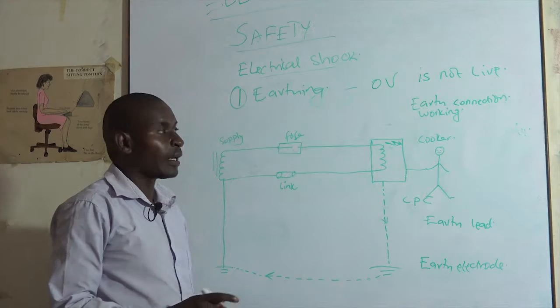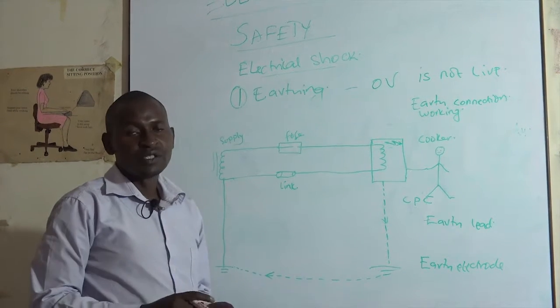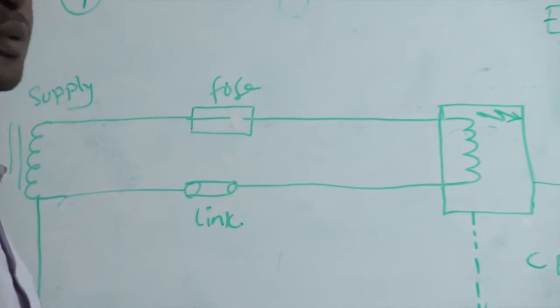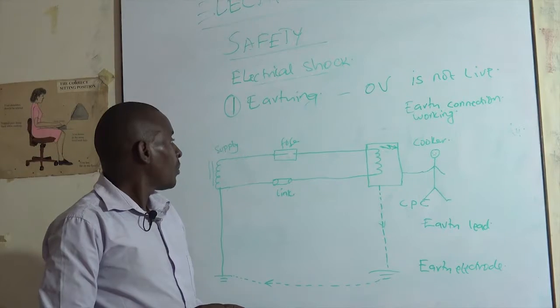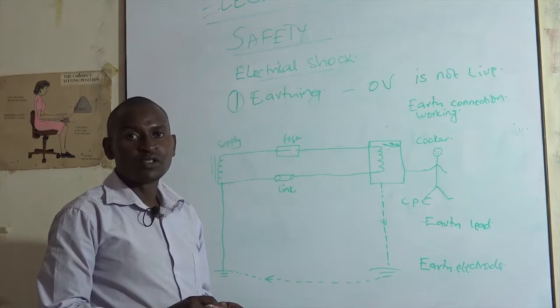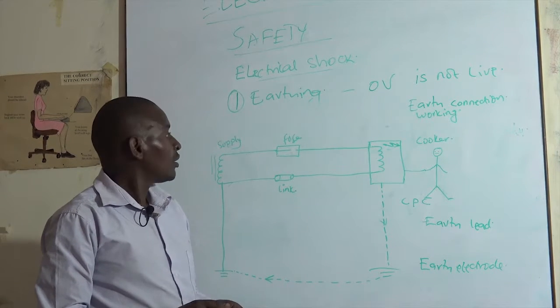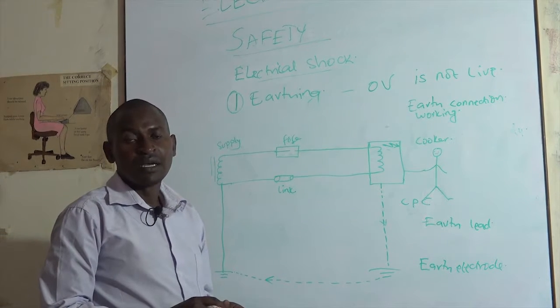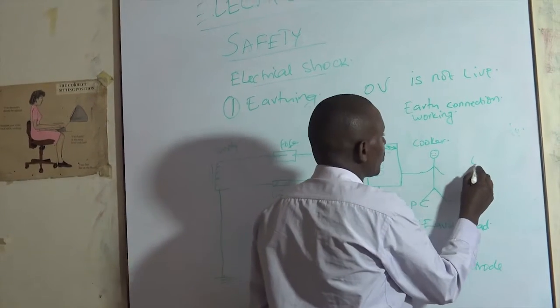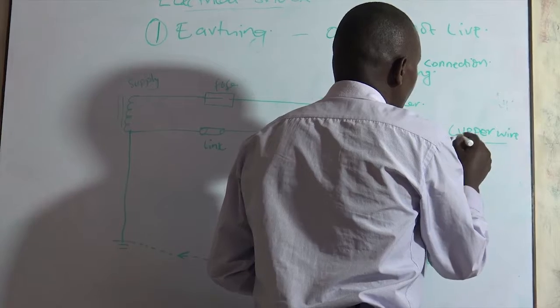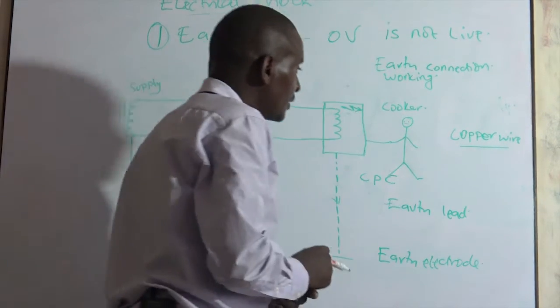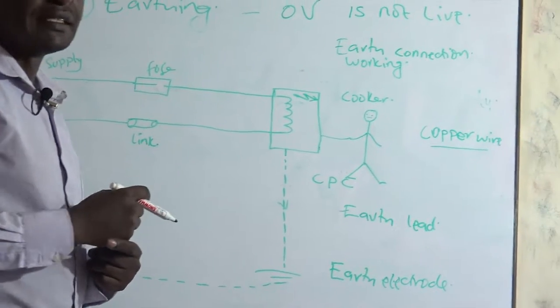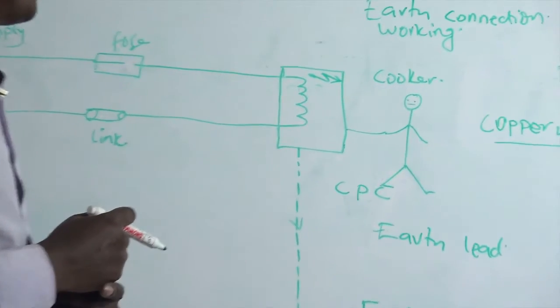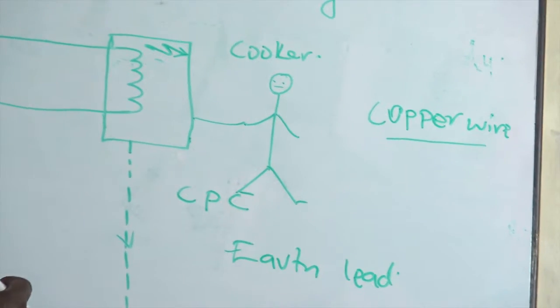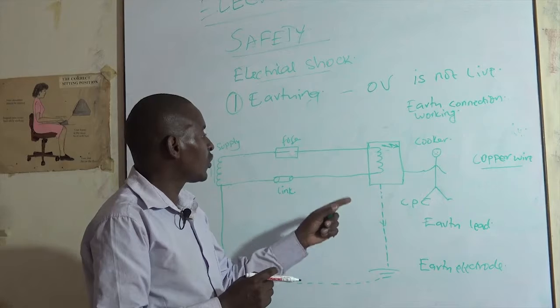The other issue should be on the protection or the protecting equipment. That is the fuses and the circuit breakers. The circuit breakers have no problem because there is no risk of someone tampering with them. But when it comes to fuses, most consumers don't follow the proper routine of replacing the fuse. They just take a bare copper wire and replace the fuse. This is very dangerous because the copper wire may not be able to isolate the fault in case of a short circuit or another fault like this.